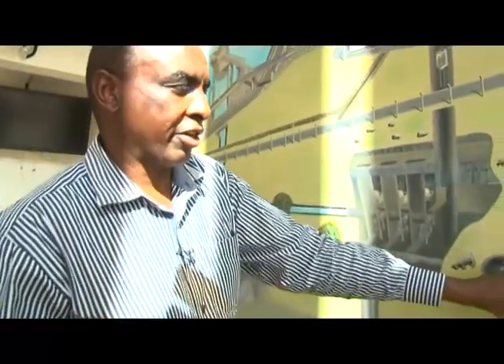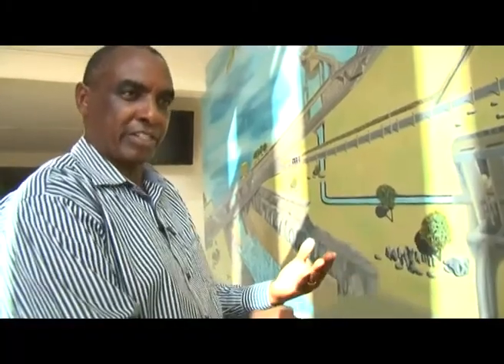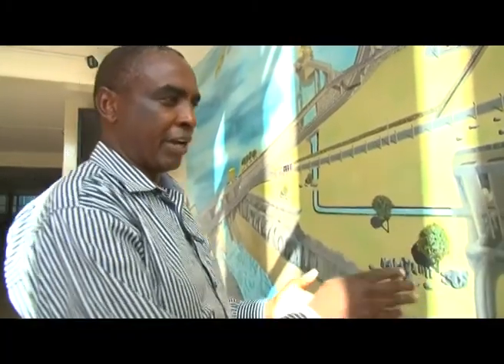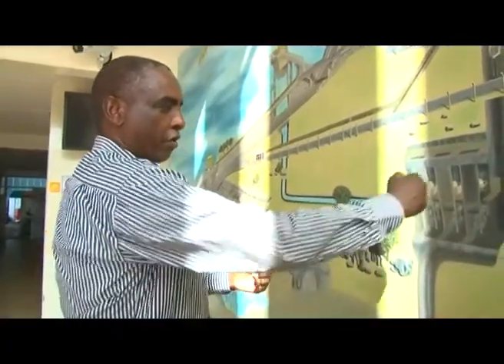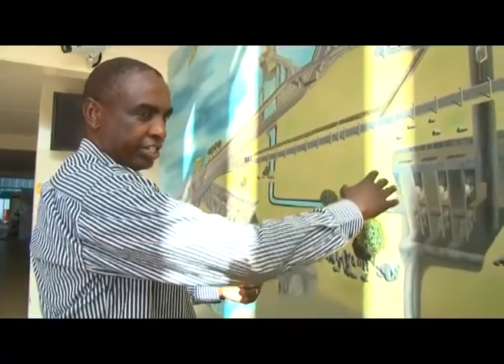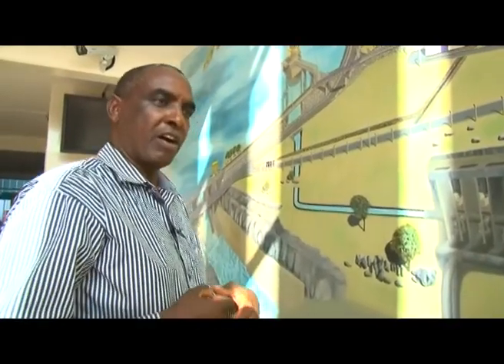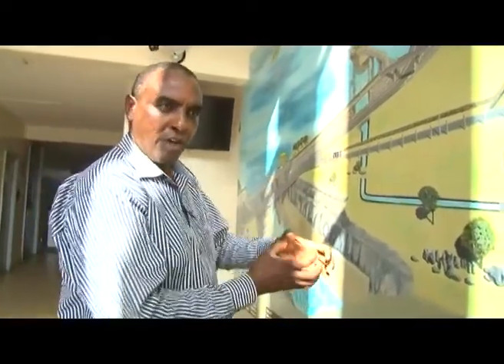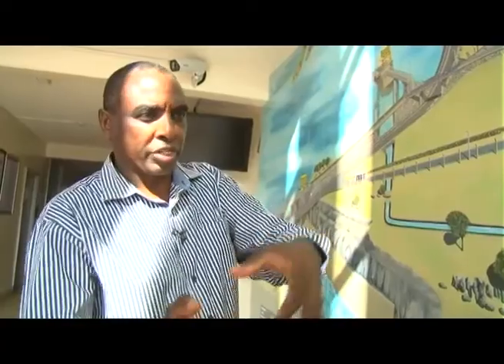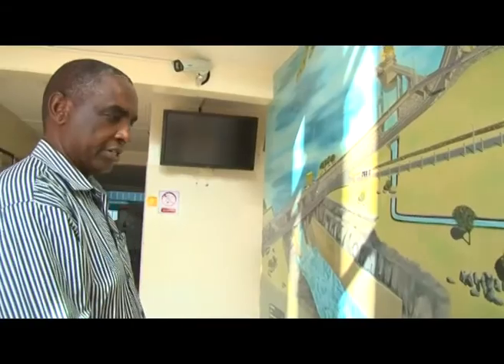This tunnel here we call the surge tunnel. When a machine is running, water pressure oscillates — it moves up and down. The surge tunnel is there to relieve those pressures so the water isn't working against the machines. Even in a sudden stoppage — if the machine was running and stops — the water momentum tries to come back. The surge tunnel relieves those kinds of water stresses.